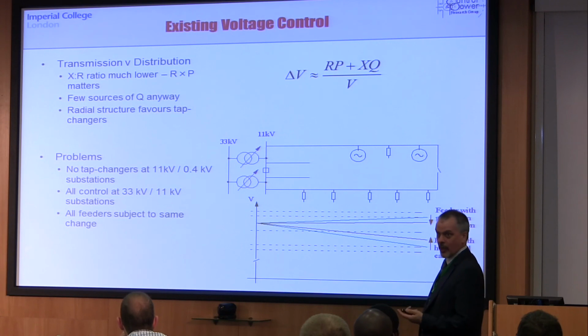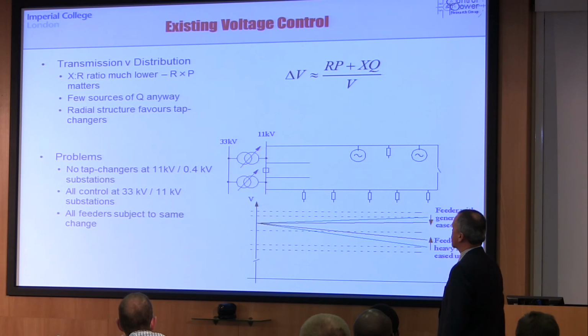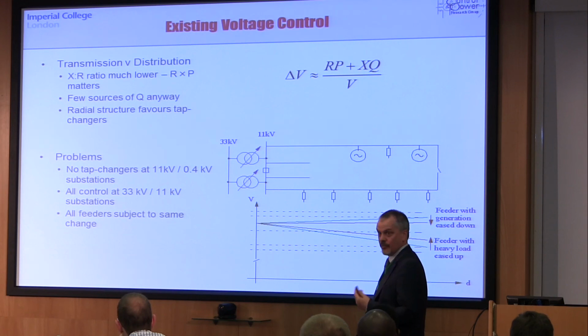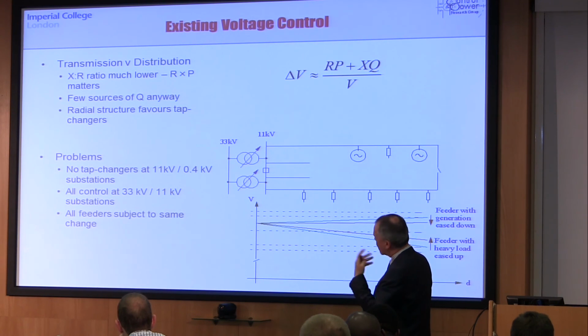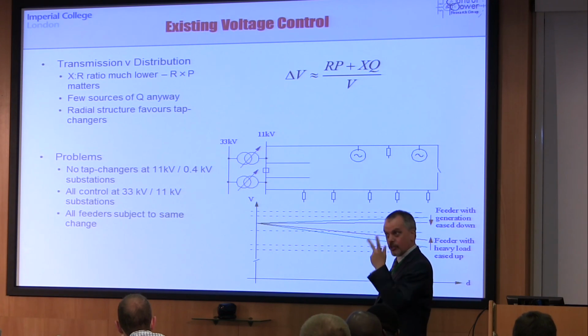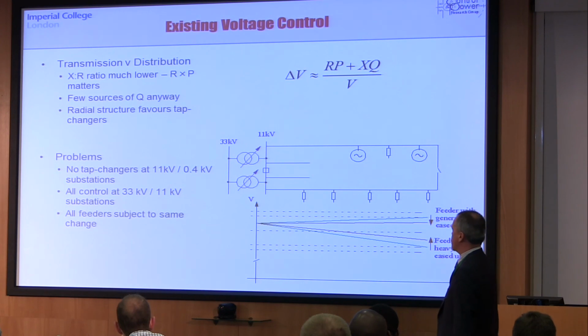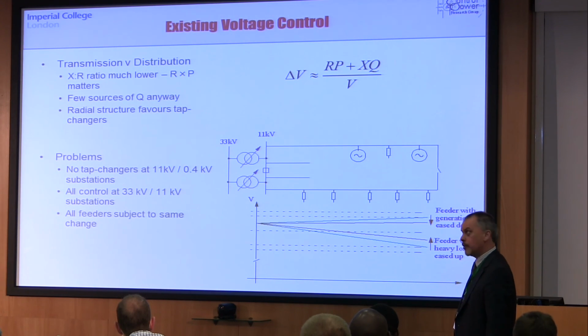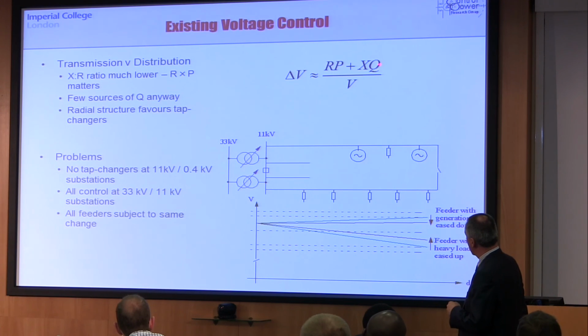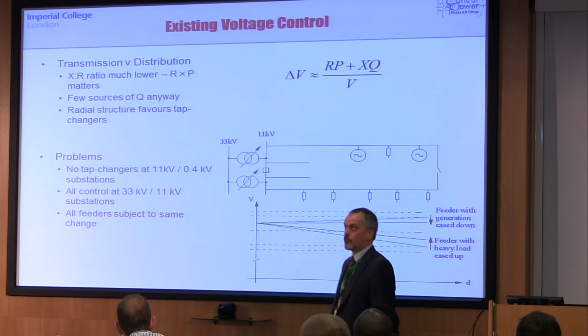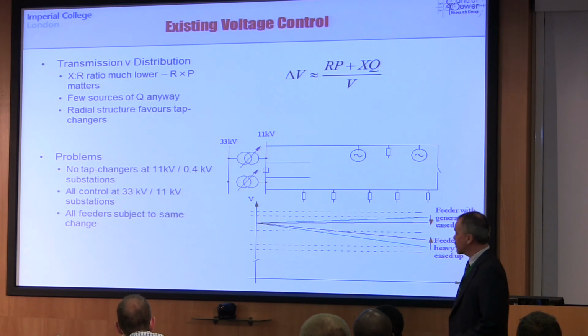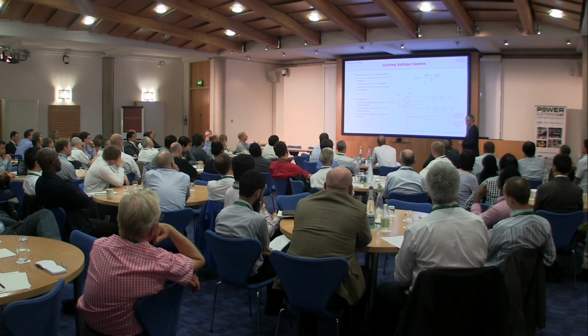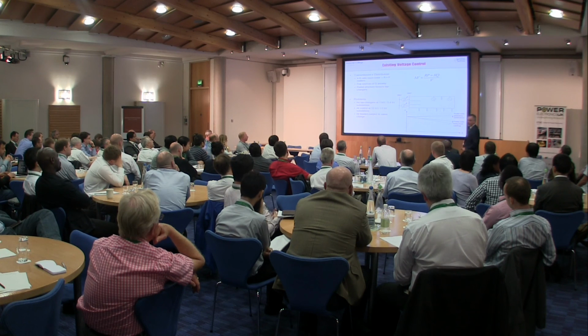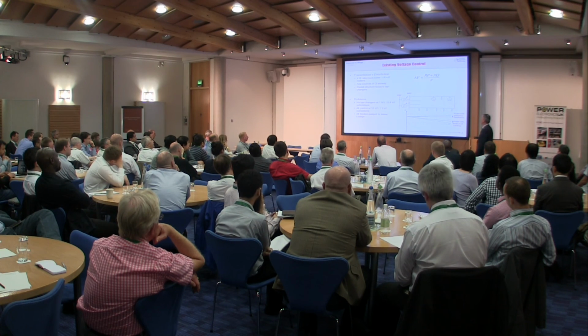It means we put less reliance on the use of reactive power to control voltage, and we've probably got fewer ways we can intervene with reactive power anyway. And that comes back to what I said earlier about perhaps distribution StatComs, reactive power devices exist. We haven't seen widespread deployment of them because our problem is as much that as it is that. And the radial structure of the network suits the use of tap change transformers. All of our feeders tracking, or a feeder tracking back to one substation where we can make an intervention with a tap change transformer to change the voltage.